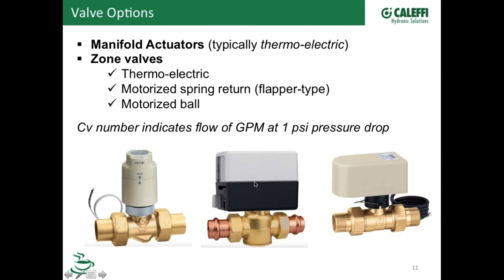Probably the go-to zone valve, I would say, in the industry is this type of valve here. This is a motorized spring return valve. So you apply power to this valve. The motor in there spins that valve open. I think of this as a flapper type of valve. There's actually a little flat EPDM, peroxide cured EPDM in the Caleffi valve that just motors open and then the spring closes it back against the seat in the other end of it. A lot of choices in sizes and voltages and stuff on that. We're going to talk more about that individually here in a minute. Then that is available, I think it's available in 5 different Cv ranges. I'll show you those here in a picture next, the difference between the Cv ratings on that.